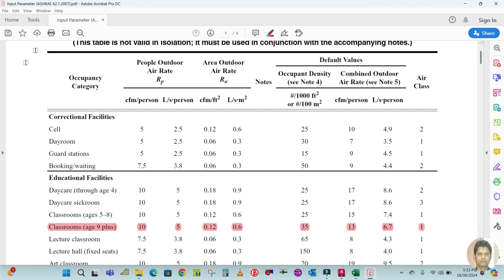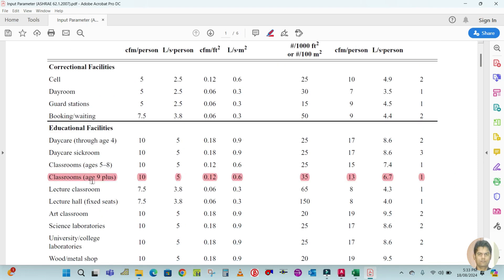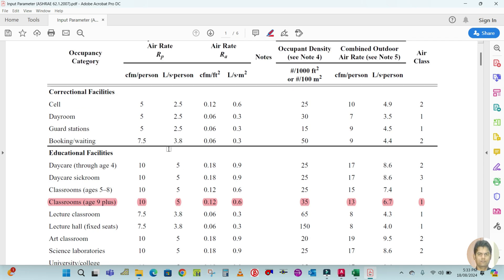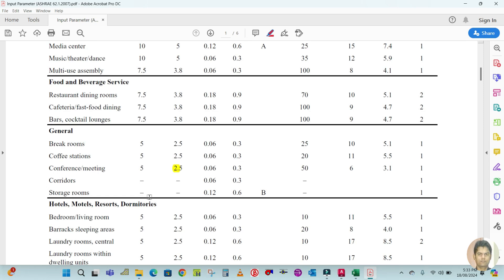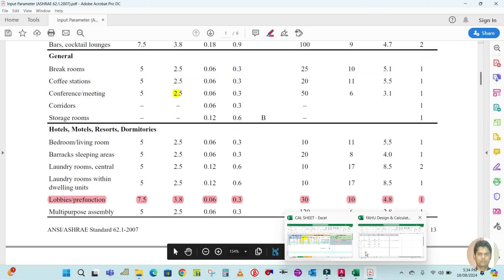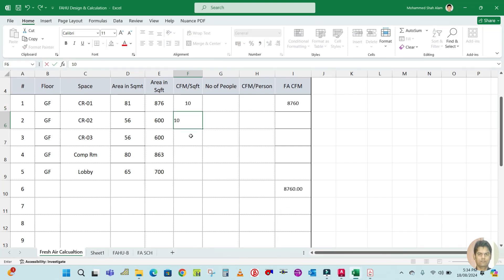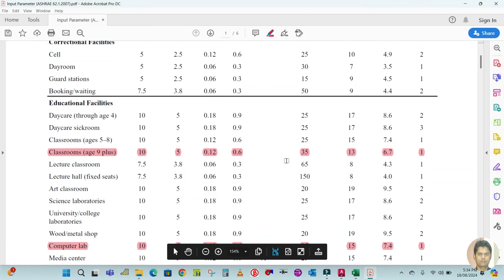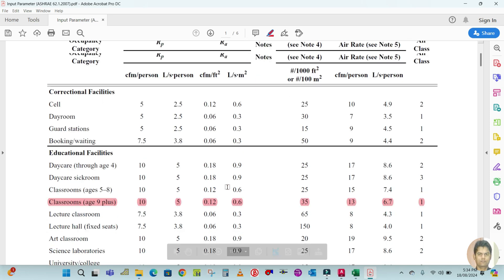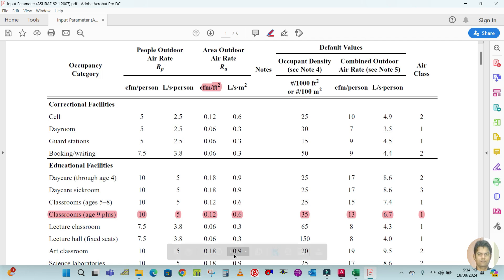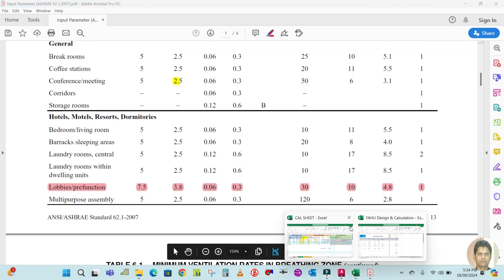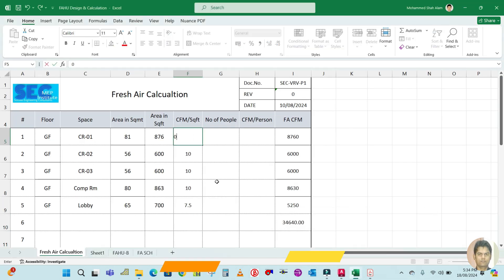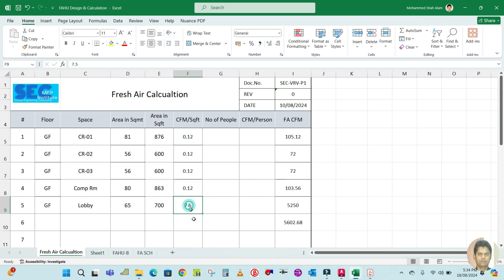From the table, the CFM per person for classrooms is 10, for computer lab is 10 as well, and for lobby it is 7.5. The CFM per square feet for classrooms and computer room is 0.12, and for the lobby it is 0.06. Enter these values into the respective columns.